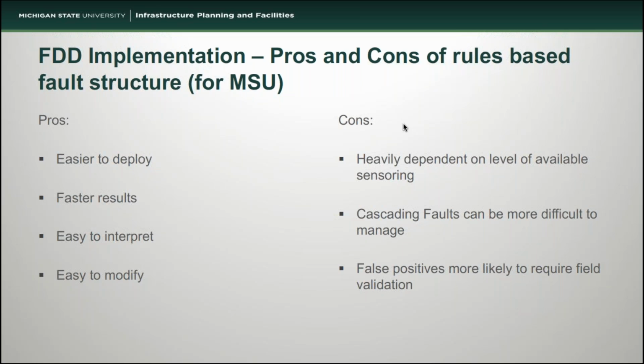And a cascading fault example would be if I have a building in the summer that receives cooling from a chiller, and that chiller fails, then we're not going to have the cold water that we need in order to cool the air in all of the air handlers. Well, all of those air handlers are going to trigger a fault saying that the chilled water is not operating the way that it should. And if I have faults at the room level, they're all going to say, hey, we're not able to cool down to our cooling set point, there's a problem. And that could be hundreds of faults that get created when it's really just the chiller that's the problem.